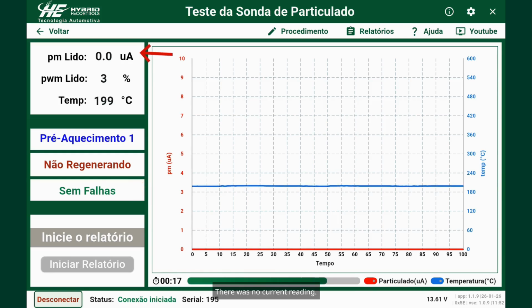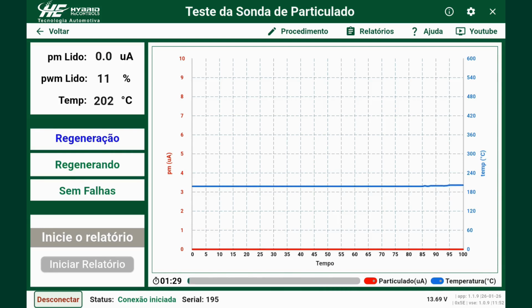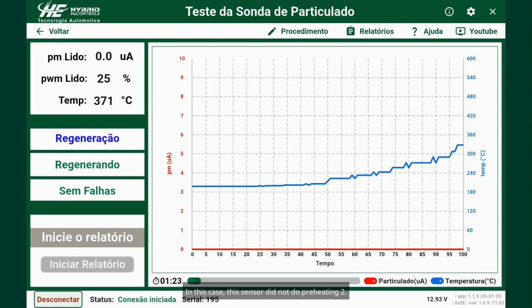There was no current reading. The temperature inside the sensor went up, in this case to 199, 200 degrees, to remove the moisture so it can get ready to take the reading. Here we can see all of this happening graphically. Here we have the timer counting the 90 seconds. It measured. In this case, this sensor did not do preheating 2.